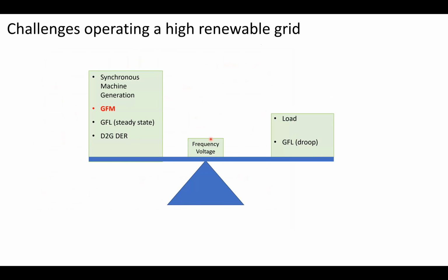So going back to my nice artwork here, up till today we consider grid forming mode inverters to be on the left side of this seesaw. As Alston was saying, it's going to help maintain that voltage phasor and act as a voltage source. And then based on the incoming voltage phasor coming into the inverter terminals, that difference in phasor voltage, magnitude, and phase angle would help to provide the P and Q output from the grid forming mode inverter with zero delay. That's the main point there.